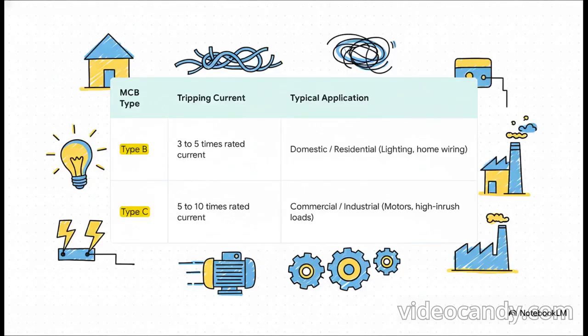So what's the big difference between, say, a Type B and a Type C? Well, it all comes down to their sensitivity. A Type B breaker, which is really common in homes, will trip when the current hits about 3 to 5 times what it's rated for. It's sensitive, and that's great for things like lighting circuits. A Type C, though, is tougher. It waits for the current to be 5 to 10 times the rated load before it trips.